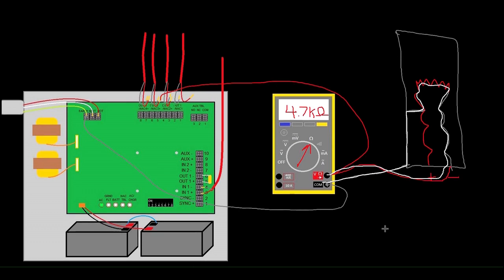So once you know you have your ground fault on that circuit, troubleshooting that hopefully is fairly obvious to you. It's going to be pretty much the same as how we troubleshot the open, we're just going to be metering for something else. Different people will handle this different ways. One option is to land that circuit back onto the FCPS so that when you're out in the field, you'll have voltage one way, your end line the other, and it would tell you where your short is.